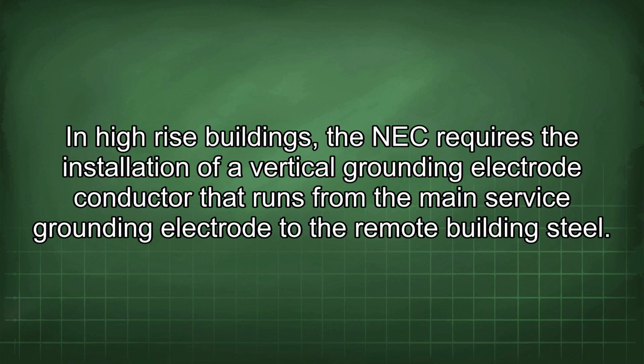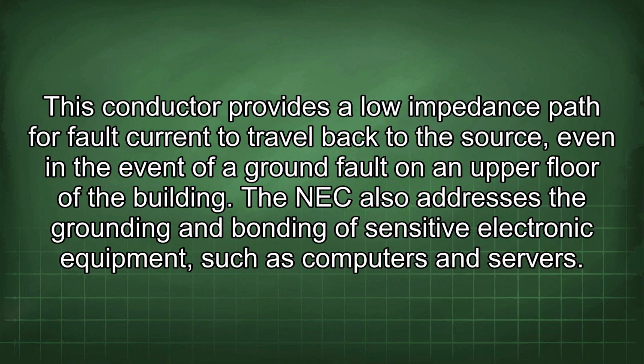In high-rise buildings, the NEC requires the installation of a vertical grounding electrode conductor that runs from the main service grounding electrode to the remote building steel. This conductor provides a low impedance path for fault current to travel back to the source, even in the event of a ground fault on an upper floor of the building.